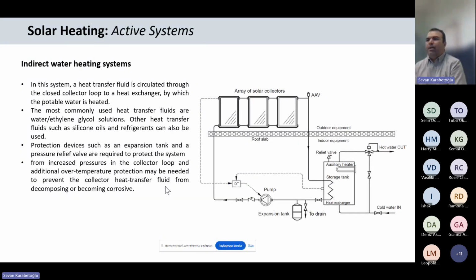And then for the indirect water heating systems, the heat transfer fluid is circulated through a closed collector loop to a heat exchanger, not directly. Commonly, heat transfer fluids are glycol water solutions to prevent freezing. Other transfer fluids such as silicone oils or refrigerant can also be used. Some protection devices, such as, again, an expansion tank and pressure relief, are also required to protect the system from increasing pressure of the collector loop, and protection against overshooting of temperature should be implemented.